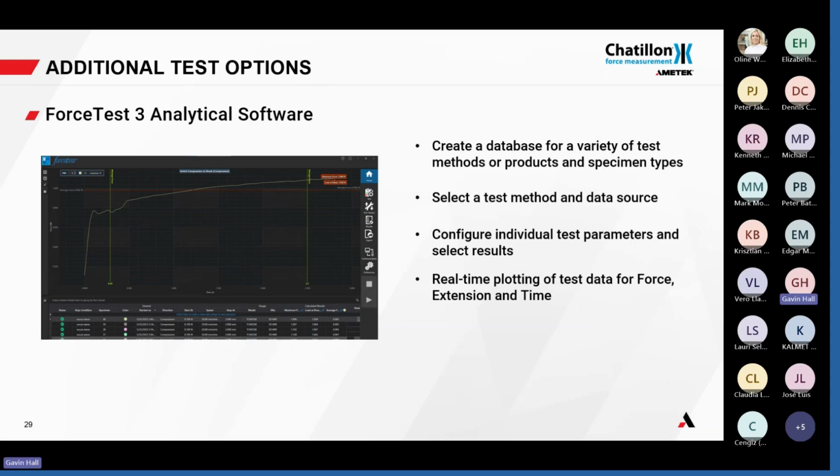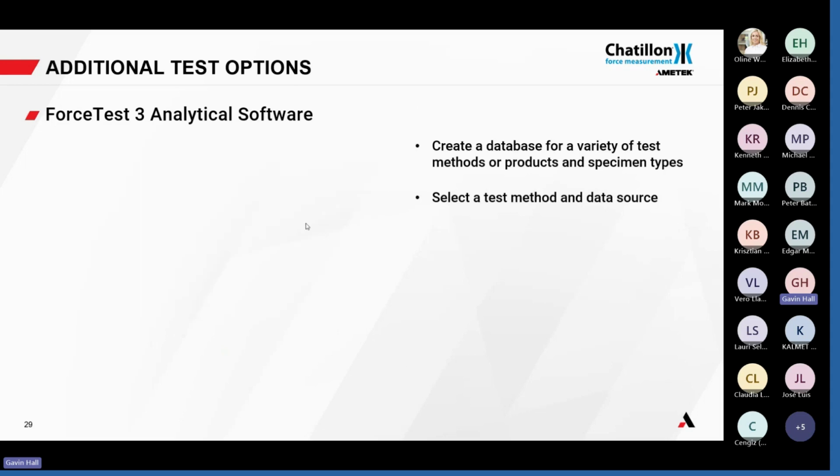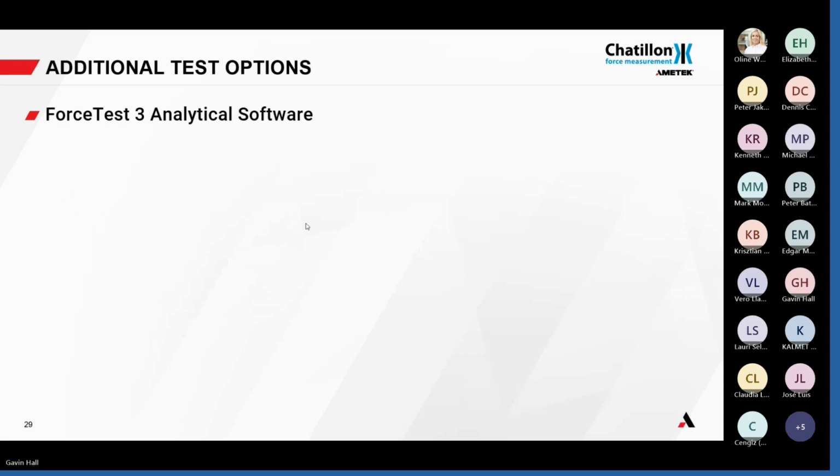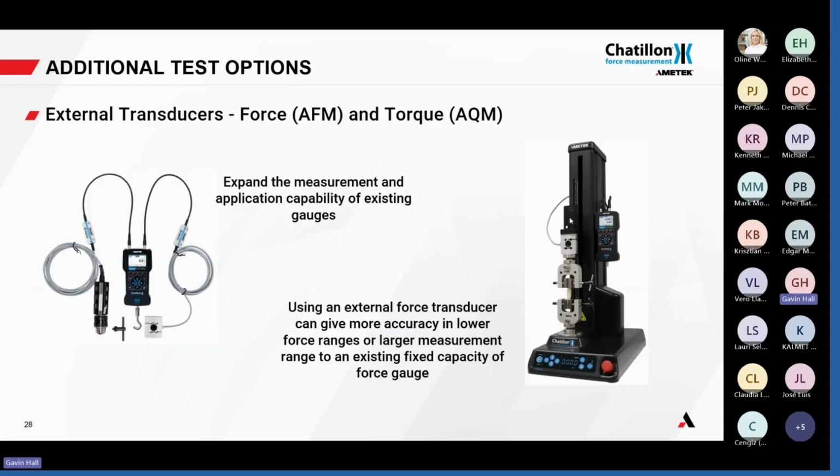And Dennis asks, how does the TCM measure extension? Well, when the TCM is connected to the force gauge, let's see if we've got a picture of that. When it's mounted to the main frame, you can see on that graphic, it's very small, but there is a force measurement, and below that there is an extension measurement. There is an encoder in the test frame.